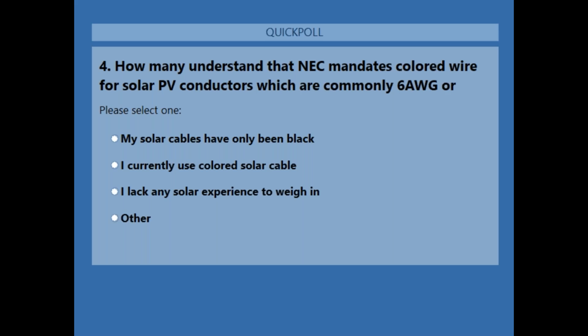I've only used black solar cable. I've been using all black solar cable up until this year. But it really doesn't matter, because regardless, solar cable is a specialty cable. It's like high voltage, it can be rated up to 2,000 volts. It's rated for outside of conduit, so its cable jacket is super thick because of the voltage and because of its exterior environmental rating.